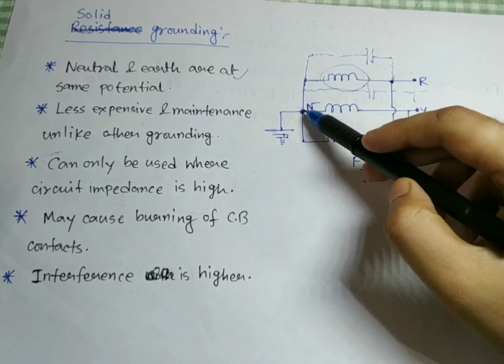The fourth point is that it may cause burning of circuit breaker contacts due to the high fault current, as I have already mentioned. And the last point is that interference is higher, because your fault current is very high in magnitude due to the low impedance. So obviously the electromagnetic interference with other communication lines can be very high compared to others. Now let's draw the phasor diagram and understand how the arcing ground phenomenon can be prevented.